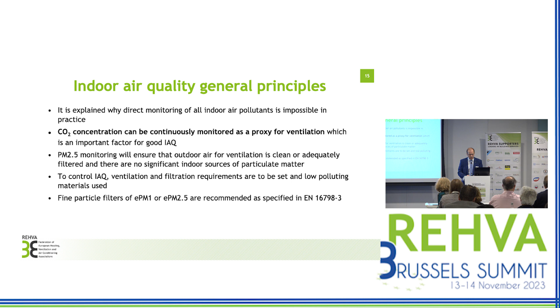Then in the directive there is a very good principle for these zero emission buildings that should be measured at relevant unit level. So basically this guides us to measure these IAQ parameters in continuously occupied spaces, like this room here, for instance. So we speak about classrooms, offices, meeting rooms, restaurants, kitchens, shops, gyms, rooms where we expect to have continuous occupancy, and in some small rooms indeed it's not worth installing all of these sensors. Basically the parameters to be monitored are CO2, temperature, relative humidity, and PM2.5.